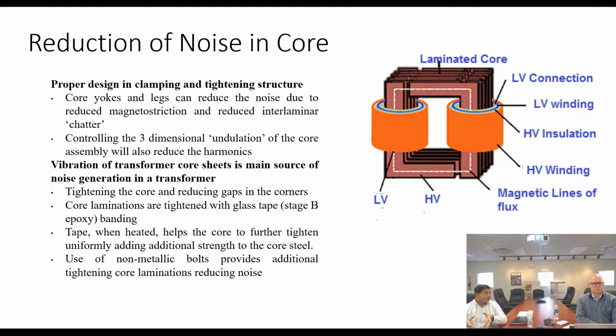Use of non-metallic bolts through the core is really normal in transformer design, where the core is tightened through the bolt, which means that in the center part of the core we also put some bolts, so that we provide more clamping and less of the bending effect on the core clamping structure. That's to provide uniform clamping to the core, and a tightened core will help to reduce the vibration, and eventually help us to reduce the transformer noise. Yeah, that's pretty self-explanatory, I think. Yeah. Very good.